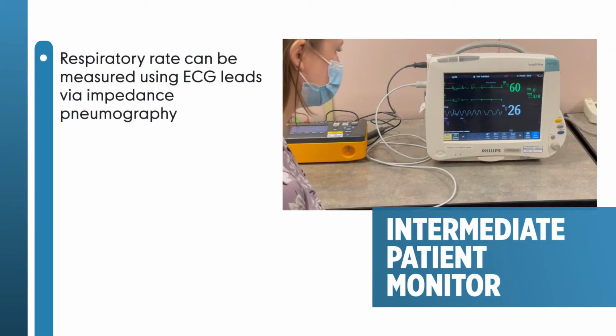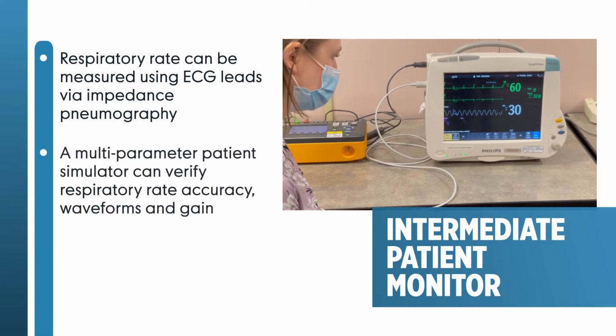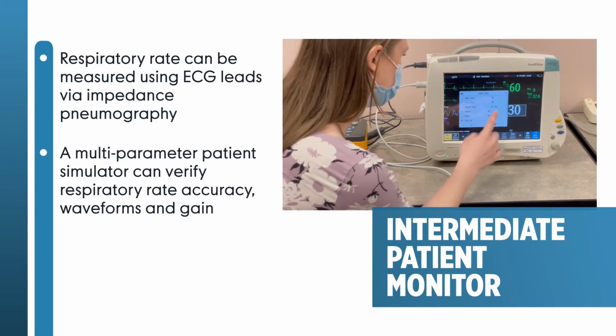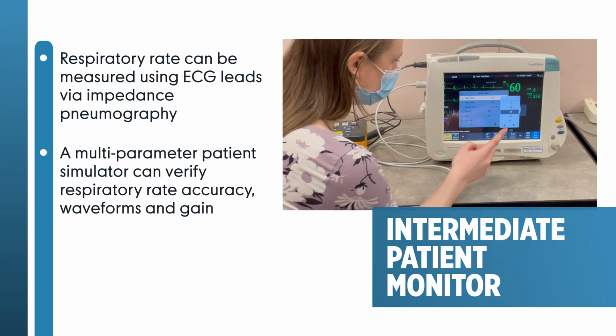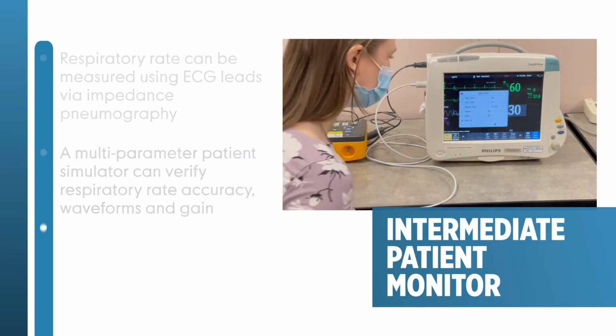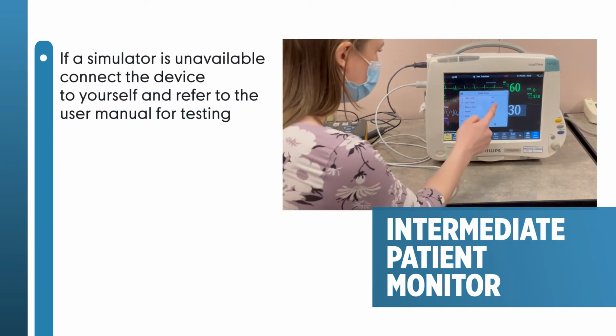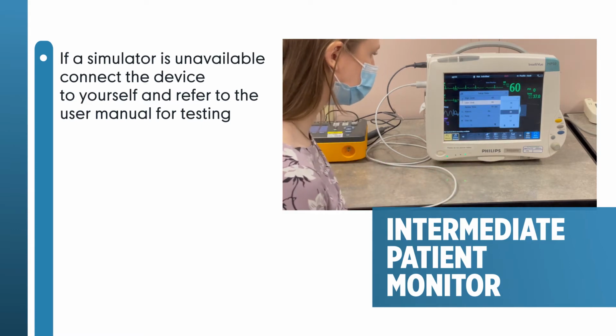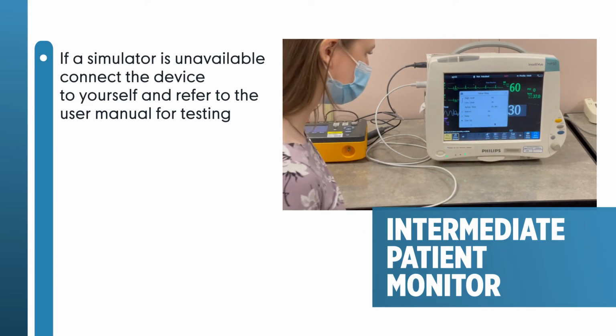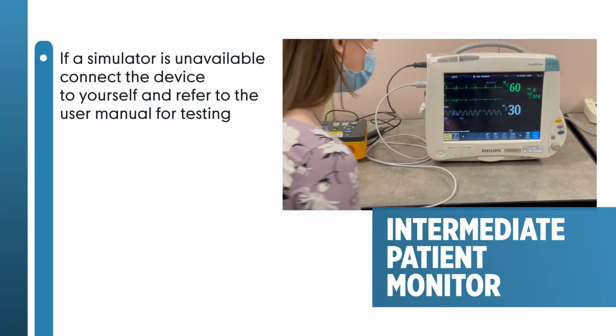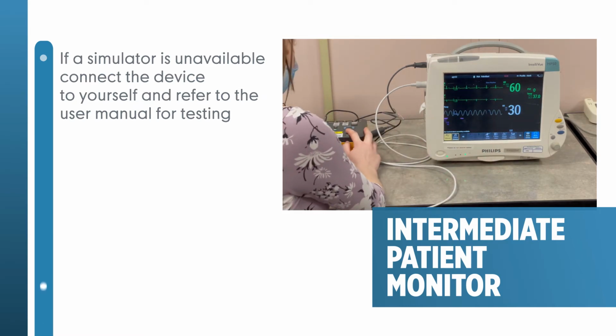Respiratory rate is typically measured using the ECG leads in a technique known as impedance pneumography. The multi-parameter patient simulator would be used to verify respiratory rate accuracy, waveforms, and gain. Again, if a simulator is not available, follow the user manual to connect the device to yourself and observe the respiratory rate versus your breathing rate along with waveform clarity.